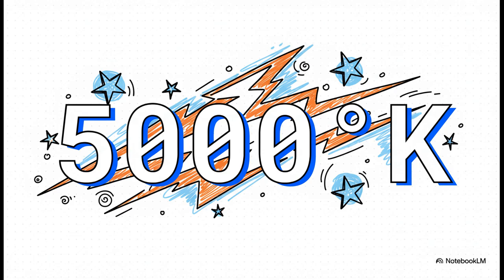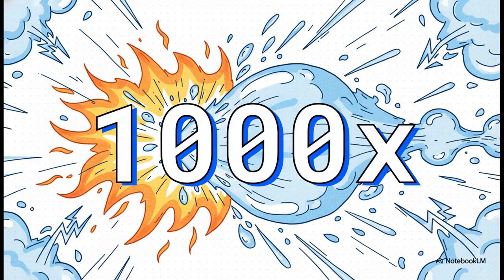Just insane. That crazy intense heat instantly vaporizes the oil right around the arc. It basically boils it and breaks it down into a huge bubble of mostly hydrogen gas. This bubble expands to about 1,000 times the original volume of the oil, creating a massive high-pressure blast inside the breaker.